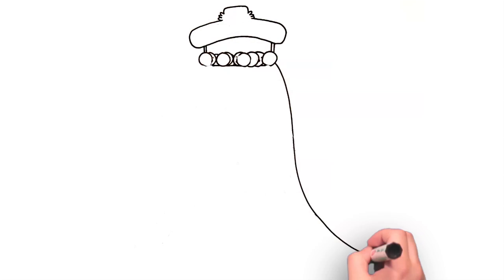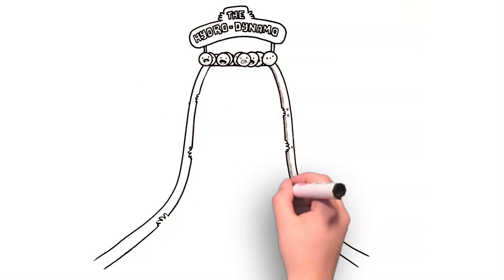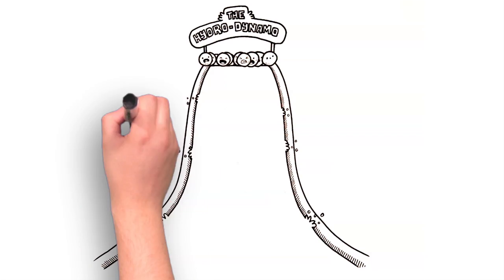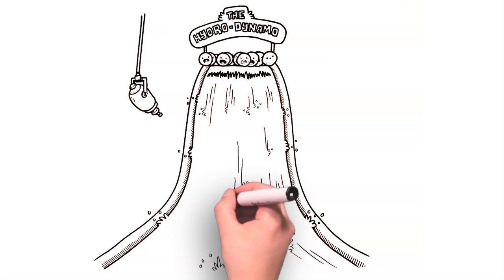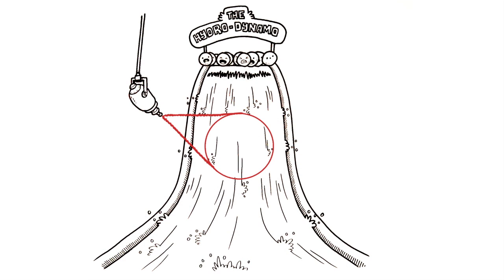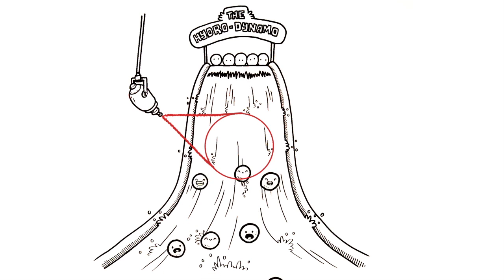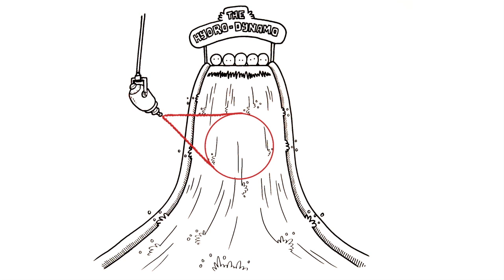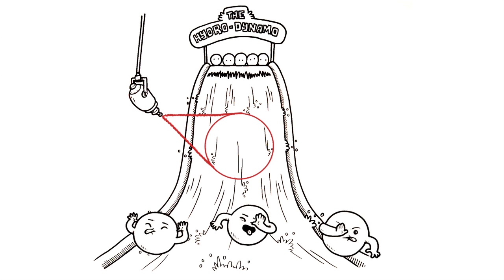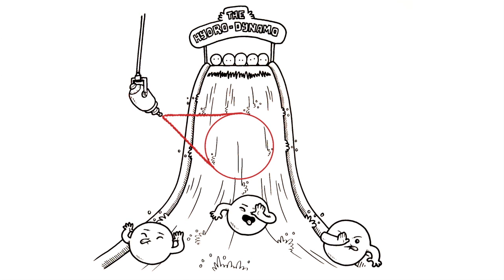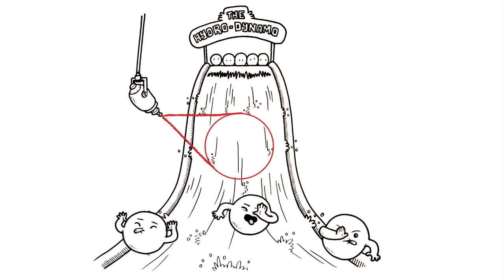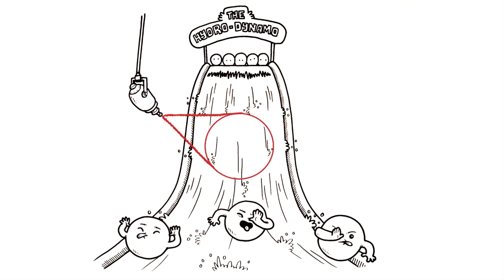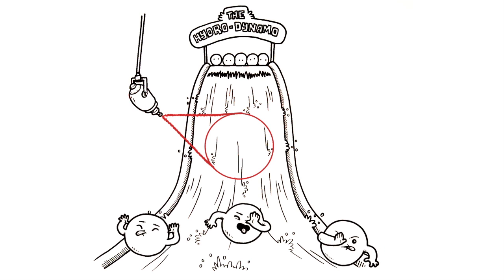The challenge with this system is that as more sample is added, the core increases in diameter, potentially forcing cells to pass through less intense peripheral regions of the laser's path. Effectively, this approach limits the amount of sample that can be passed to a maximum of about 150 microliters per minute. Not bad, but not great.